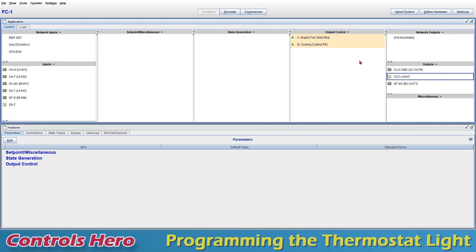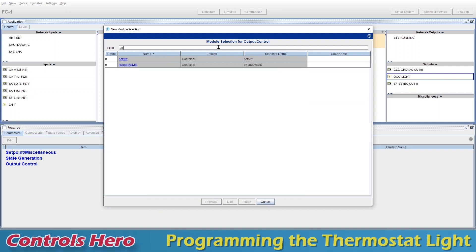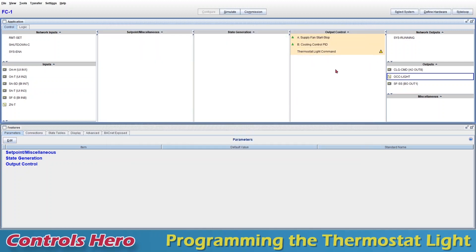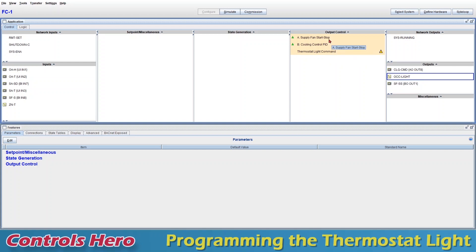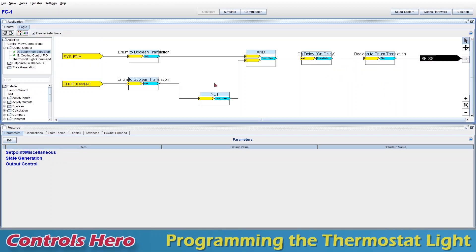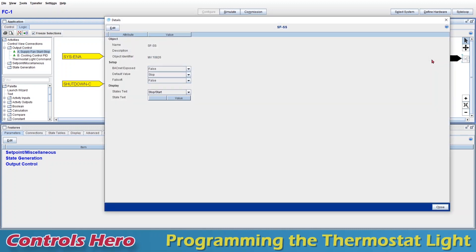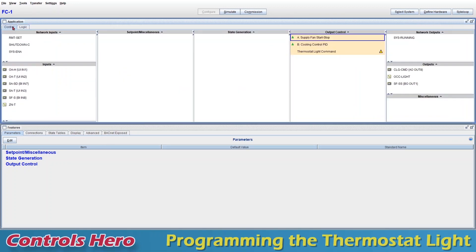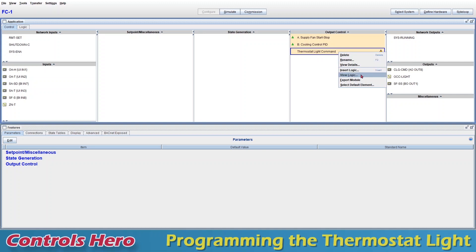Now we want to create a new activity by clicking at this plus sign. I'm just going to type activity or the first letters, click one, I just want to add one. I'm going to name it the thermostat light command and finish. Now before going into my new activity, I want to know how I'm going to connect my fan start stop to my light. I right click on the supply fan, view logic, and I can see I have my supply fan start stop command right here. If I double click on it, I want to look for the units. It has the units of stop start and it's a multi-value. So stop start, that's all I want to remember. I'm going to close, go back to my control logic, click on my thermostat light, right click, and go inside view logic.